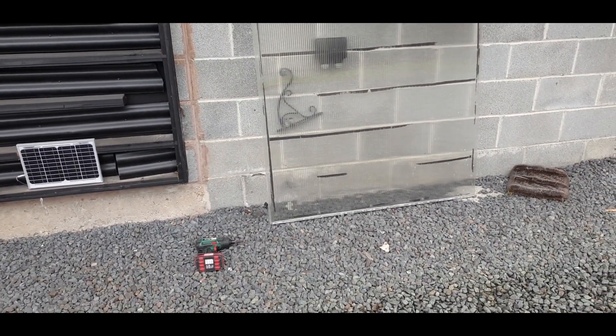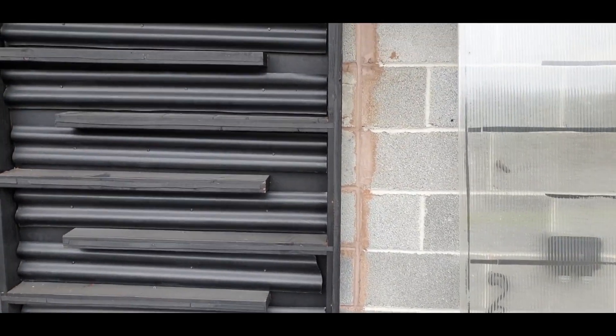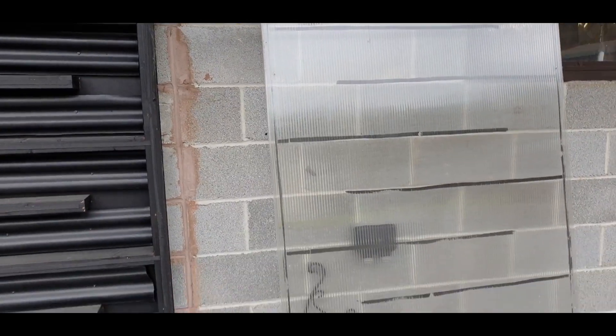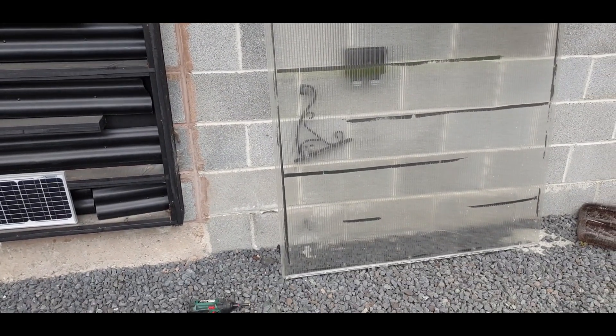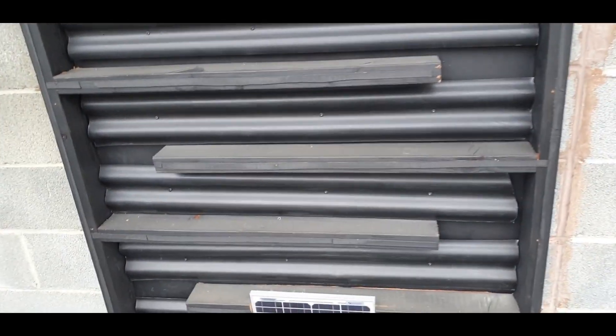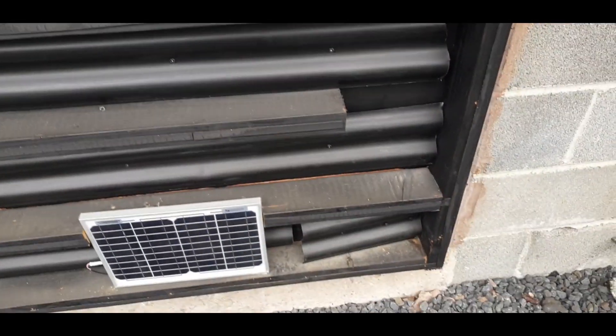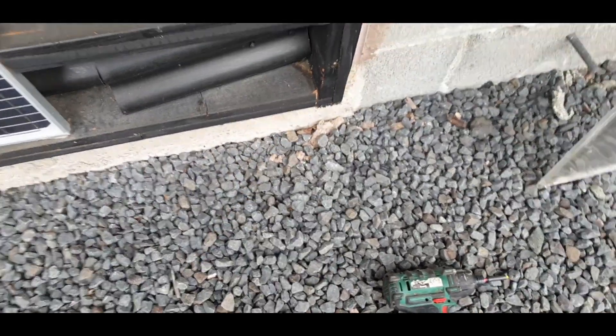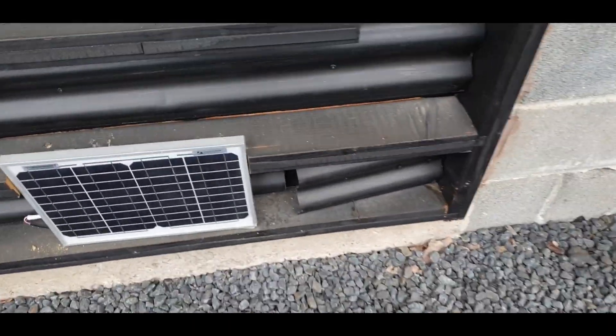That's the cover off and you can see the tape has parted company a bit, so I'm going to have to put some new tape on there - it's got a little bit crispy in the sun. That tape's probably not designed for UV exposure. However, it's not too bad in here really - it's the same as the other one, just a lot bigger. There's a bit of old tin roof and a lot of sawdust in there - that's the downside of it being in the workshop - but it's basically the same principle.